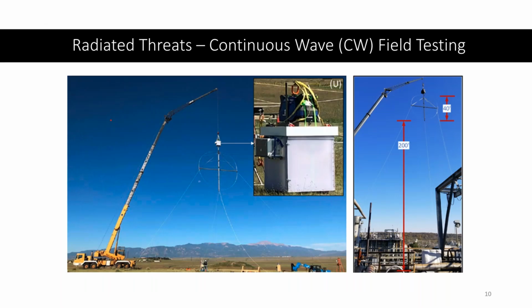There we go. We'll go to the CW test. Another test that uses radiative testing is this continuous wave test. This is an external test. It's not in the lab. It's not designed to stress the device to see whether it can handle it without being destroyed, but rather it is testing that transition from radiative to conductive. So you look at how much energy can actually get into or be coupled with the device.